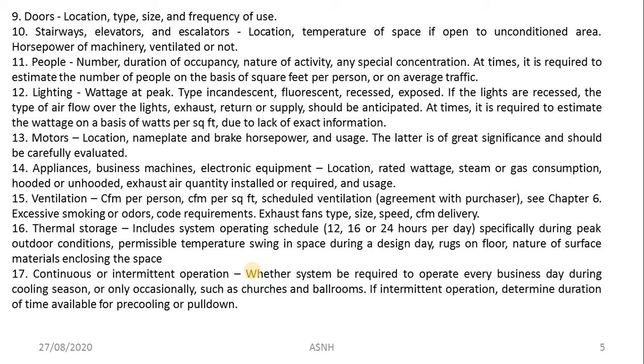Thermal storage also plays an important role. The system operation schedule — whether 12, 16, or 24 hours per day, especially during peak outdoor conditions — must be considered when designing heat load estimation. Similarly, continuous or intermittent operation must be assessed — whether the system operates every business day during the cooling season, or only occasionally, such as for churches and ballrooms where people gather only once a week or on special occasions.